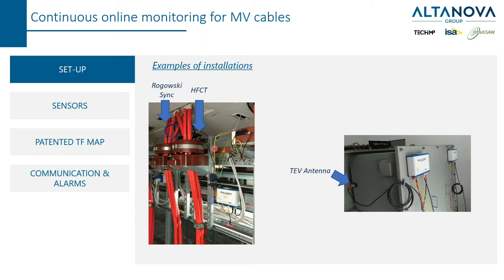This yellow ethernet cable is used to connect Falcon to the substation bus. This is a Rogowski coil used in this case to take the 50 Hz synchronization signal, and this is the HFCT connected around the shield of the cable. In another example, Falcon is placed on the metallic enclosure through magnets, and the TEV antenna sensor is also placed through magnets.